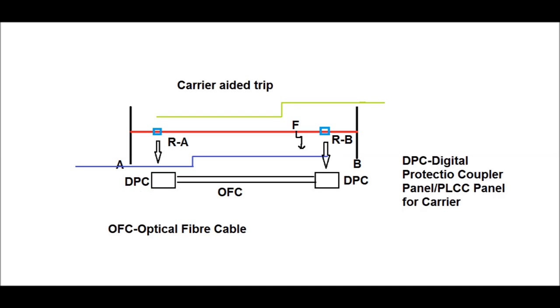What is the function of the carrier aided protection scheme? It has been shown in this diagram. A fault occurs at a point F which lies in zone 2 of relay A. That is, it will sense the fault in zone 2, but it will trip after 350 to 500 millisecond.